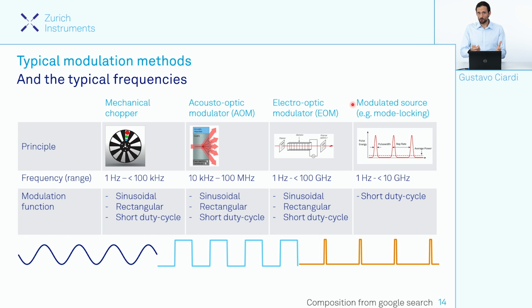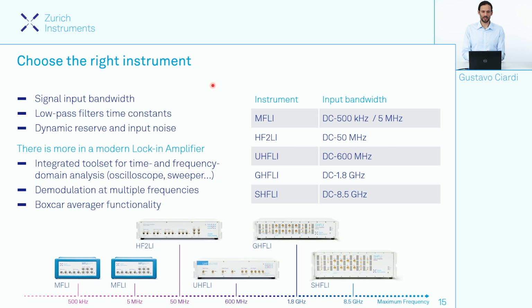Now we have our modulation. What we need is the right instrument to demodulate our signal. Now here, the easy thing would be to say Zurich Instruments lock-in amplifiers are the best, but this is not the point I want to make here. Of course, the most important parameter to choose the right instrument is the signal input bandwidth. And this signal input bandwidth must generally be higher than the modulation frequency we want to look at.